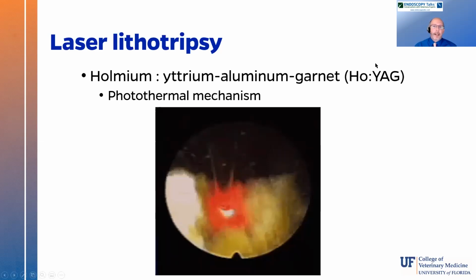Now, the difference between the holmium YAG laser and some other lasers for fragmentation is that it uses a photothermal mechanism to break up the stones. A lot of lasers create a cavitation bubble at the end of the laser fiber, and that cavitation bubble ruptures and releases a shock wave, and that's what actually causes fragmentation. The holmium YAG laser creates what's called the Moses effect. It basically parts the water at the tip of the laser fiber. That allows the laser energy to pass through the air more efficiently than it passes through saline, where that energy gets absorbed very quickly. So it allows us to transmit that laser energy to the surface of the stone.